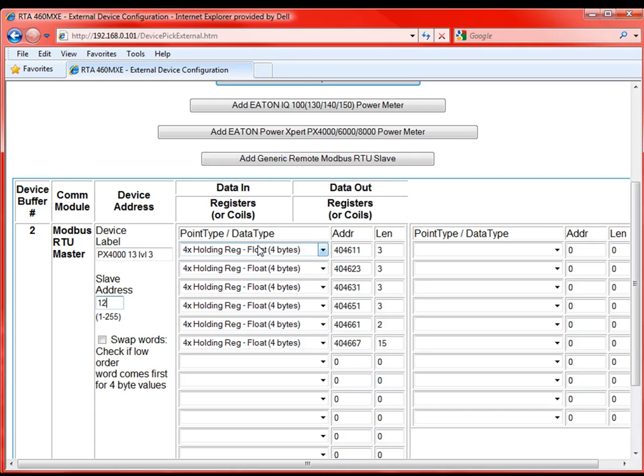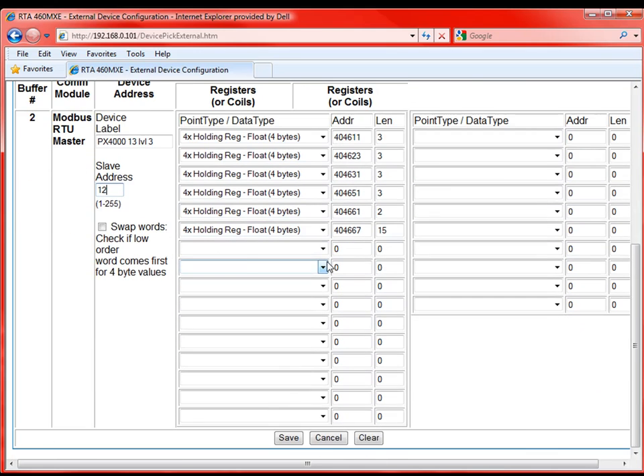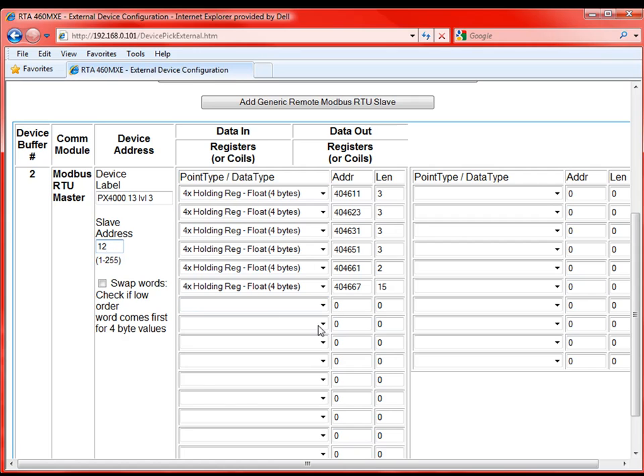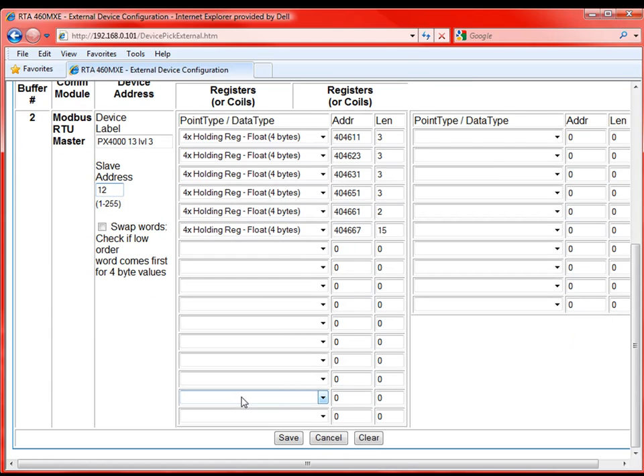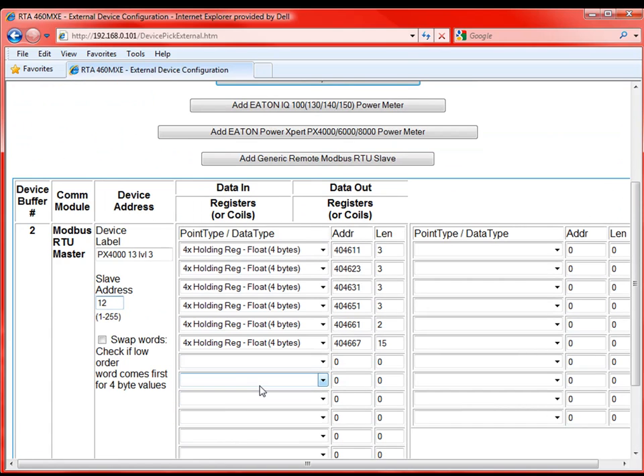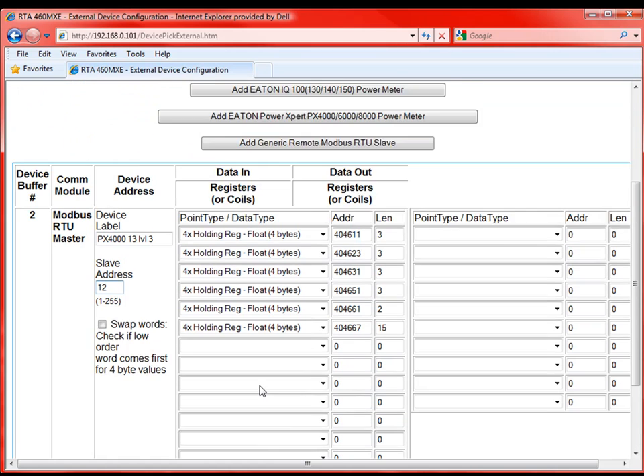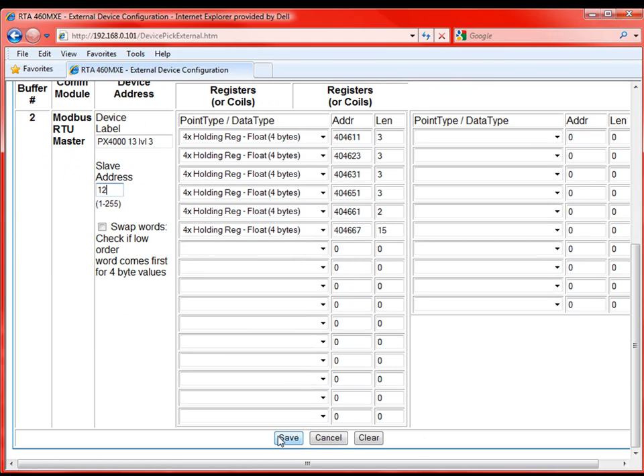Then we go to the registers. This is the data from the meter that we are presenting over to BACnet. This is all predefined. This is not all of the data that the meters present to the network. What we've done is we've taken the data that 90% of users are looking for. So these meters present a lot of data, and some of it is just, I mean it's all great data, but a lot of users don't need it all over on their BACnet side. So we've taken what 90% of users need. If there is other data presented by the power meter that a user needs to find, they are able to add additional registers here so that they could grab those points.